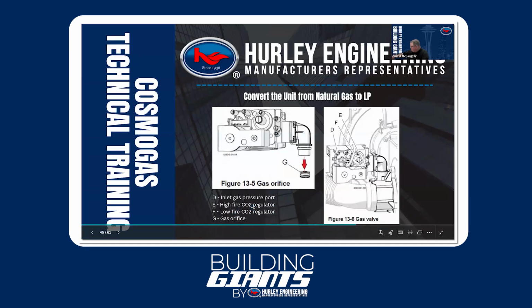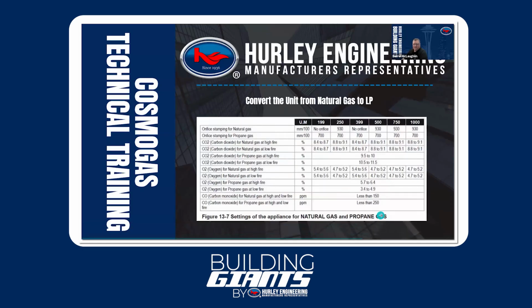So if I switch to propane, my O2 numbers are going to be a little different than if I was running natural gas. I believe we've got, yeah, here's our chart. You can see less than 250 parts per million carbon monoxide for propane, less than 150 for natural gas. And then our O2 numbers are going to run 5 to 4, high 4s, low 5, depending if you're low or high fire. They vary a little bit more for propane, but they've got them for each different fuel and for each different model. So just make sure you reference this when you're doing your startup.